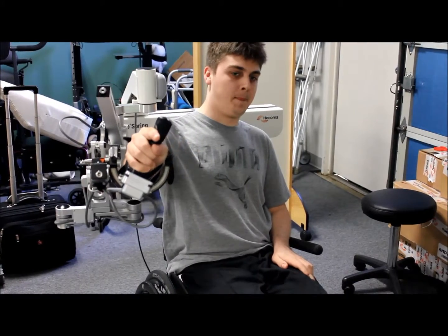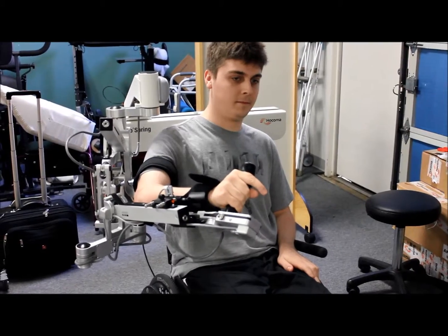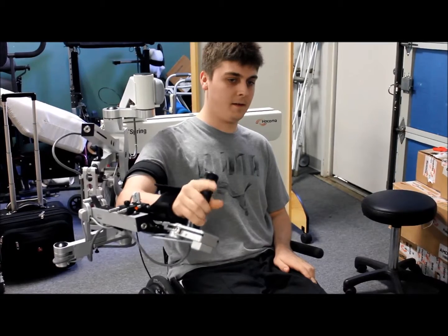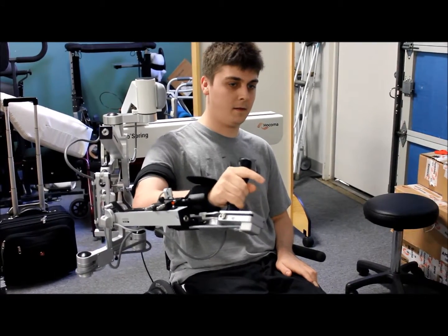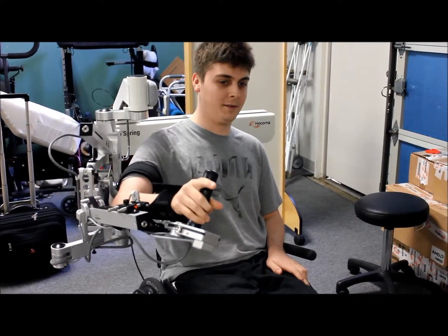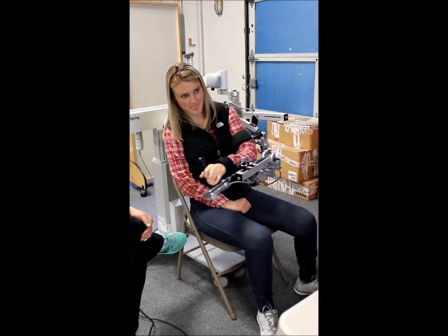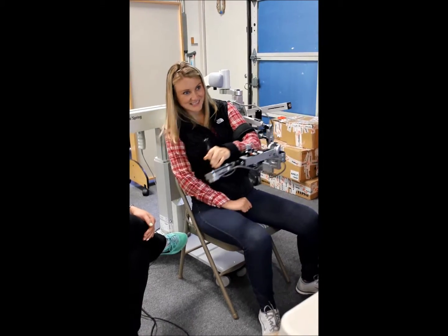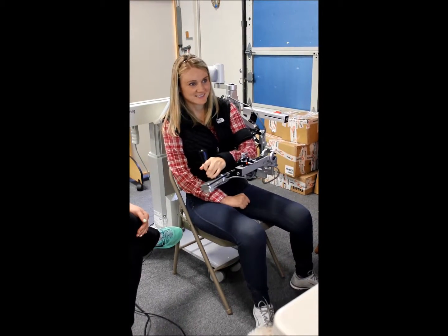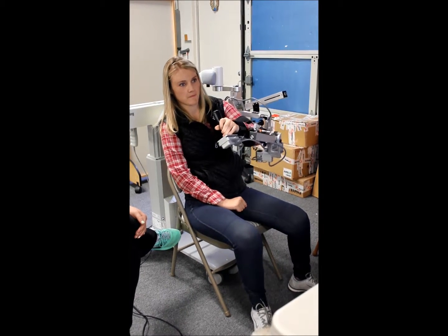Hand-eye coordination and biofeedback is a key component to relearning how to coordinate movements. By providing weight support for the affected arm and hand, the ArmeoSpring allows clients to reacquire and improve motor control. The ergonomic and adjustable arm support is an exoskeleton with integrated springs. It embraces the whole arm from shoulder to hand and counterbalances the weight of the client's arm for zero gravity, enhancing any residual function and neuromuscular control and assisting active movement across a large 3D workspace.